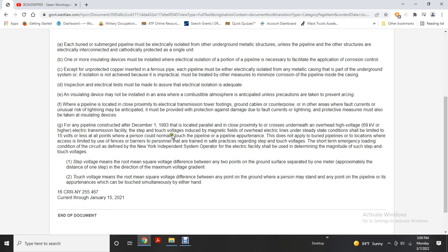Touch voltage due to magnetic fields from overhead electrical lines under steady-state conditions should be limited to 15 volts or less at all points where a person could contact the pipeline. This does not apply to buried pipelines where access is limited or where personnel are trained in safe practices regarding step and touch voltage. Under short-term emergency loading conditions, operators must determine the magnitude of step and touch voltages. Step voltage is the RMS voltage difference between any two points on the ground surface spaced one meter apart in the direction of maximum voltage gradient. Touch voltage is the RMS voltage difference between a point on the ground and any point on the pipeline that could be touched simultaneously.